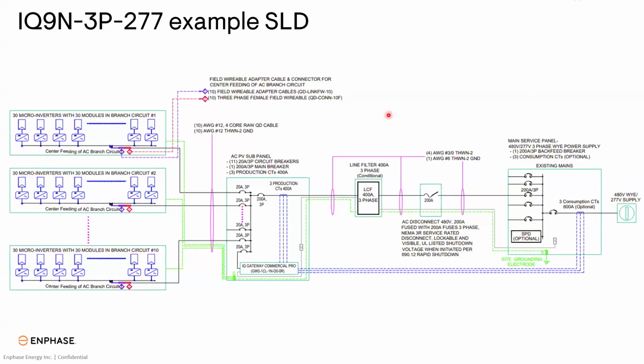We have each circuit being called out as center feeding. Again, it doesn't have to be exactly in the center. You're just pulling your home run from as close to center as possible. Then each one of those circuits comes over and lands on a 20 amp 3-pole breaker. So you're going to have 10 breakers, one for each circuit, and then at the bottom, one breaker for the gateway. So in that combiner panel, you're going to have 11 20 amp breakers total, 10 for the circuits and one for that gateway.